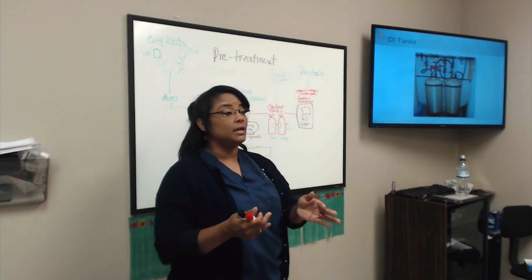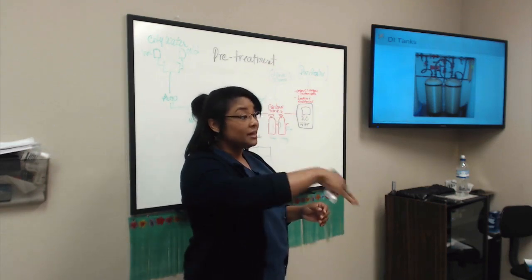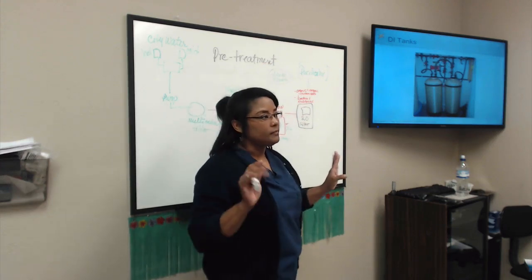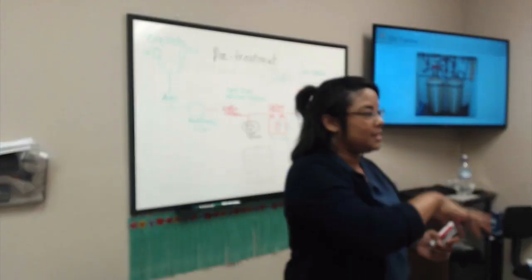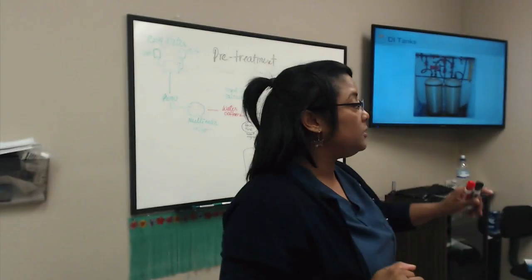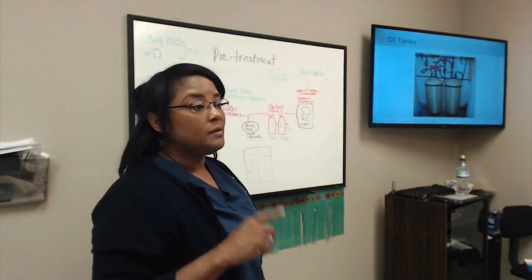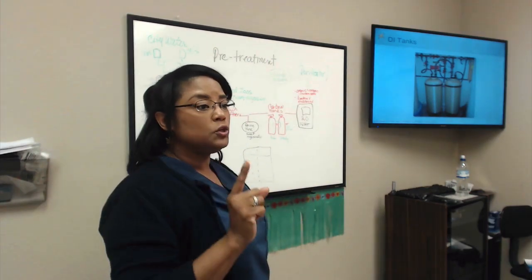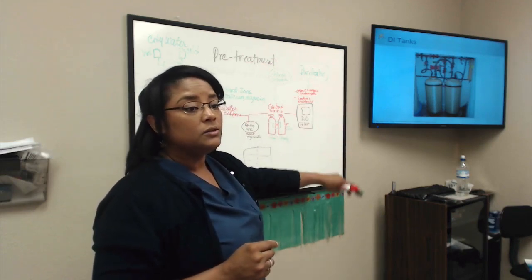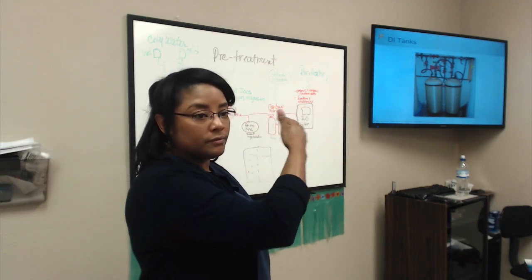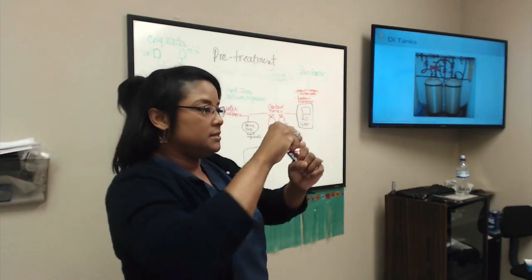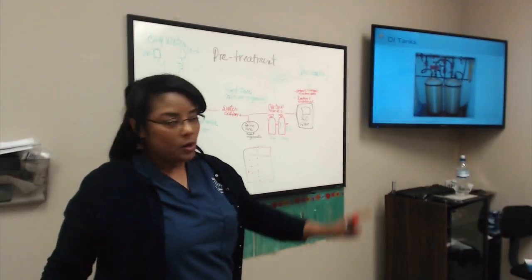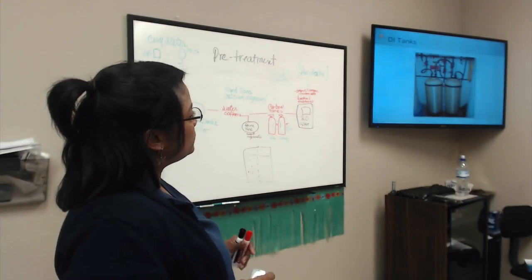But then it was a Saturday, so the biomed was going to be there on a Sunday, and he was going to work with that. So if it's in the middle of the week, yeah, the biomed has to come that day, because during the night he'll have to work with this. Okay? Because if we use the DI tanks today, we cannot use them tomorrow. And usually we only have 2 in the center, so we have to call the company that provides this. They'll take these tanks and then replace them, okay? So again, only when the RO is not working do we use the DI tanks.